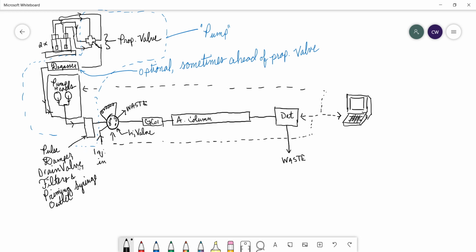And the pulse dampener also contains a drain valve and additional filtrations, and an outlet for our priming syringe in case of manual priming for the pump. This whole system, which I've outlined in blue here, is all housed in the pump for an HPLC instrument, okay? Typically, you will have the pump underneath your eluent reservoirs, so that once you get flow starting from the eluent reservoirs to the pump heads and out, that flow will continue until a break of gas, an air break, gets into the line of the mobile phase reservoir bottles.